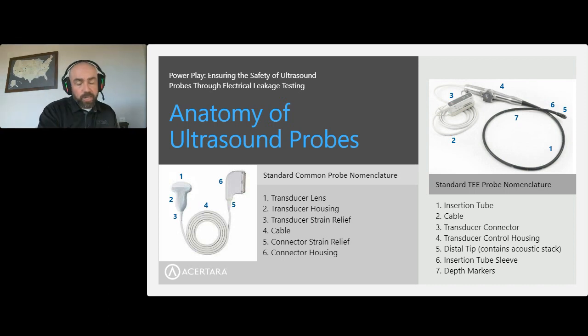Finally, next, you see the cable that I was just discussing. There's a cable sheath on the outside. That's typically a PVC material. Those will oxidize over time. They will pick up all the disinfecting solution that you put onto them, and so they tend to turn really yellow and tacky to the touch. Not great. Don't love those.